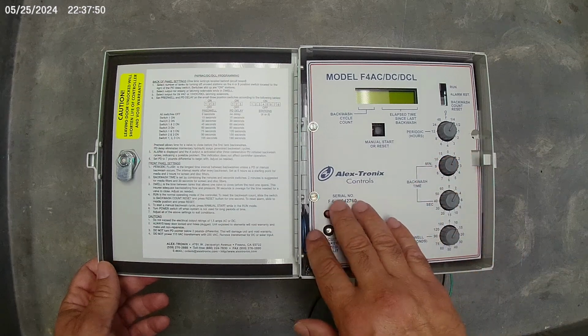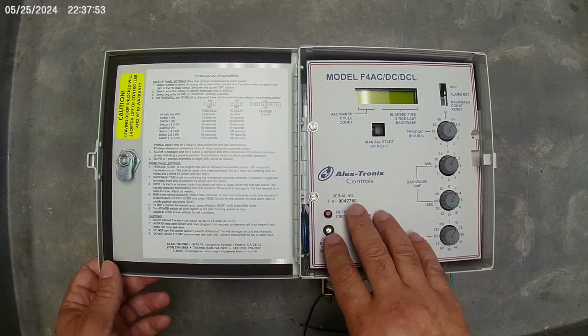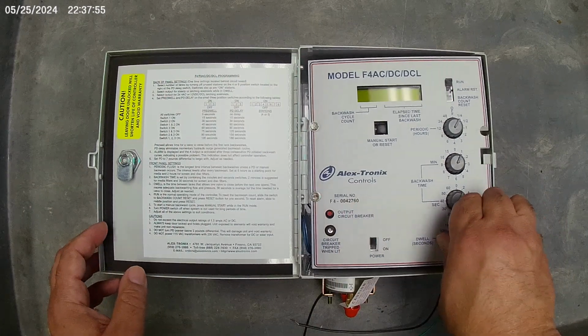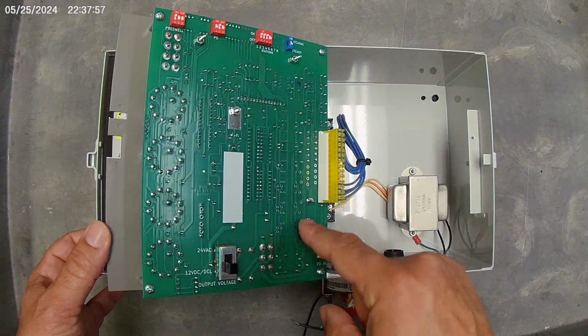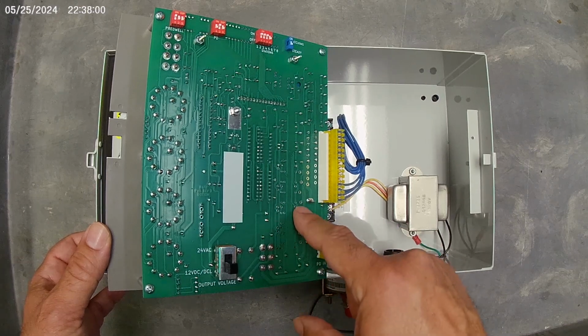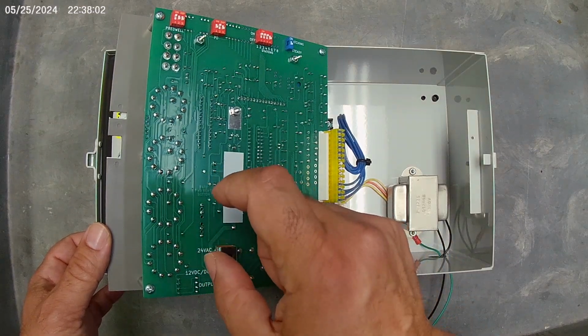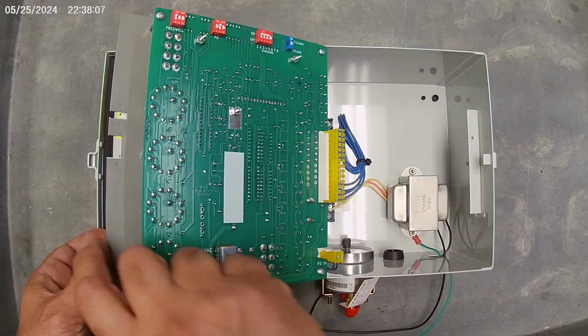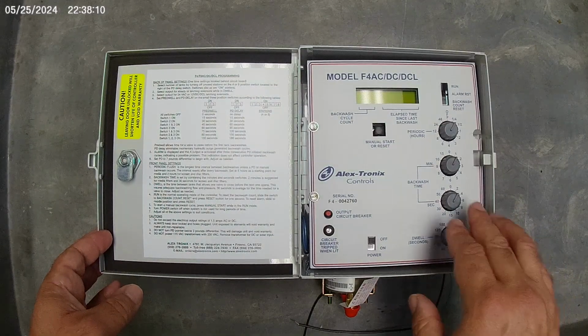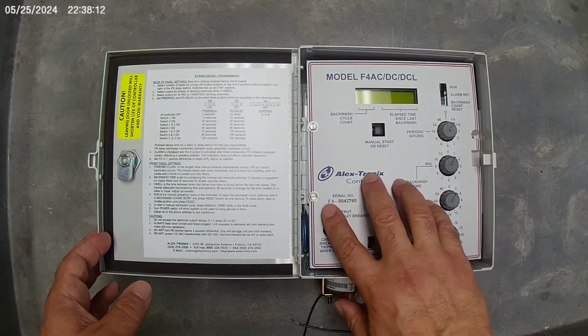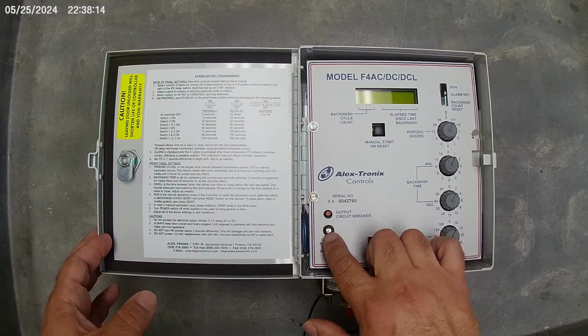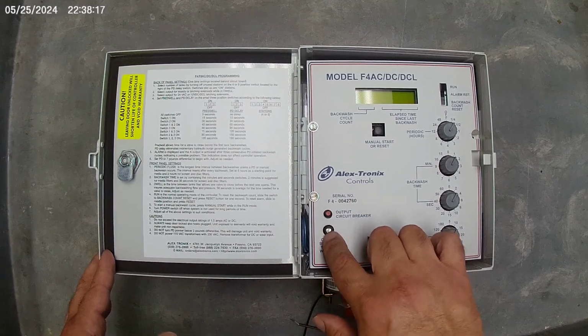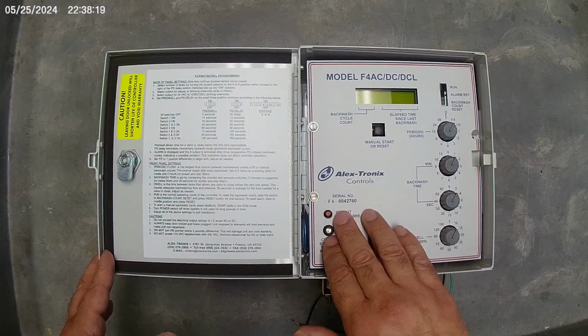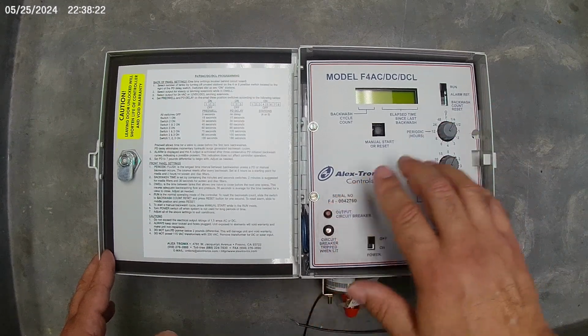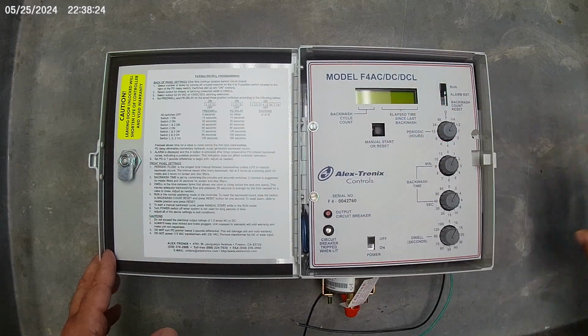Now, for a while we could not get these circuit breakers, so we actually used fuses, and those would be located in this lower portion of the back of the panel. We typically include an extra one on the back to stick in when we did use them. And then before that we had circuit breakers, but we did not have this light feature yet. So panels that are more than 10 years old may have a breaker without a light. Again, suspect the breaker if your controller is functioning but the solenoids are not.